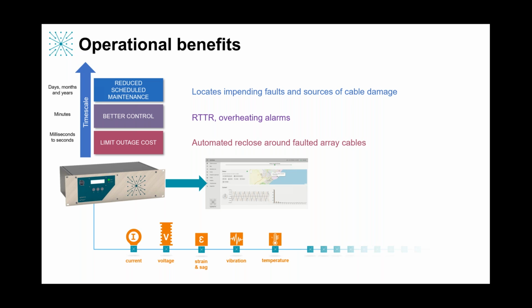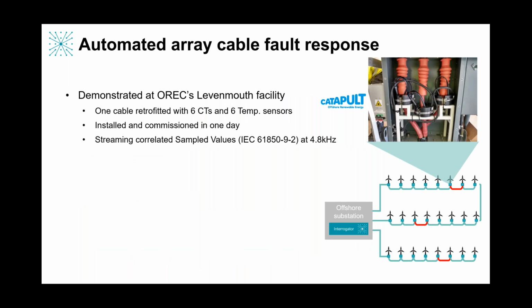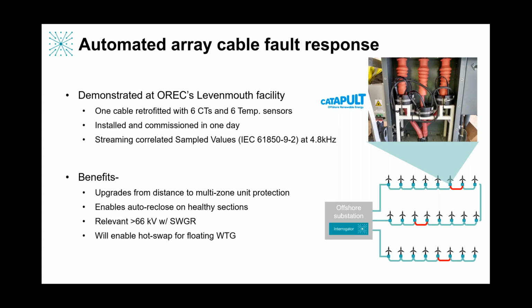So for all these reasons, this technology can play a role. But let me explain this in a bit more detail for you. So we've been working with the Offshore Renewable Energy Catapult at Levenmouth to do our first offshore wind demonstration, where we instrumented array cables. So in a typical string of up to 8 cables, we can instrument all of them with one system, and you're basically upgrading from a distance protection scheme to a multi-zone unit protection scheme. So if there's a fault in an individual cable, we can isolate that cable, reclose on all of the other cables and turbines and keep them in production, limiting the fault and limiting the outage time while repairs are scheduled.